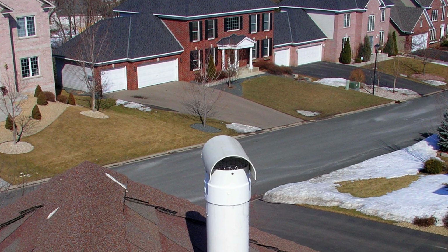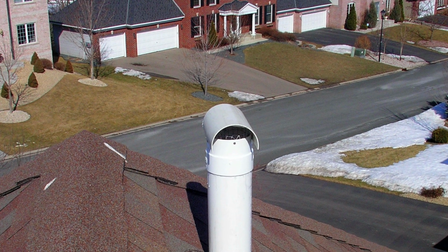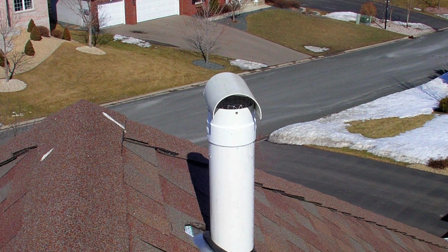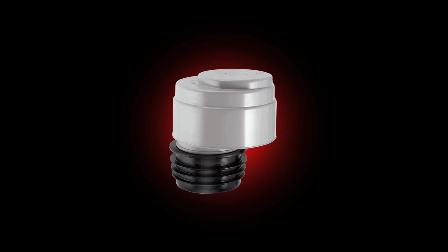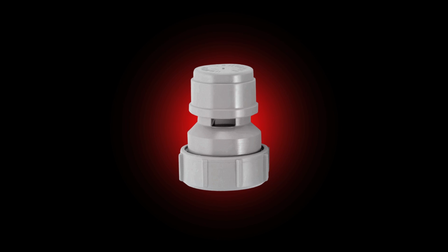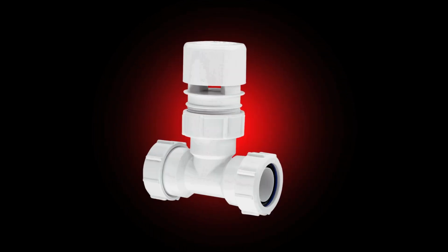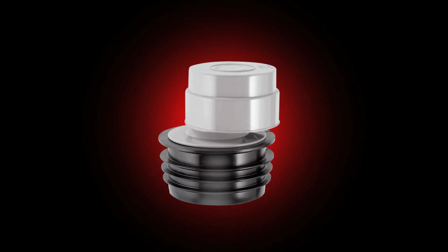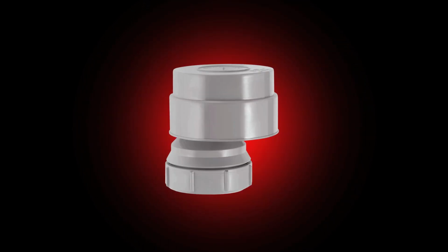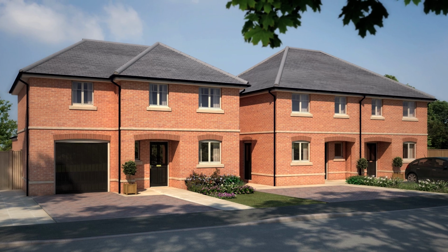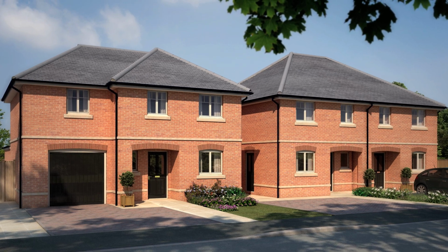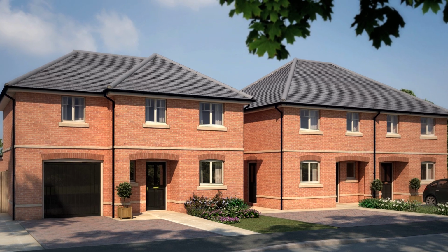Plumbing waste pipework needs to be ventilated to relieve positive and negative pressures created by the flow of liquids through the pipes. McAlpine's solution to plumbing ventilation is the air admittance valve, or AAV. These are pressure-sensitive one-way mechanical vents. They eliminate the requirements to terminate the vent stack above the roof, meaning the pipe can be terminated inside the building. McAlpine have been at the forefront of this development for almost 50 years.